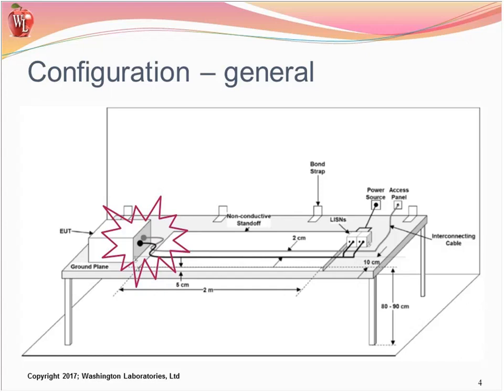Now, in the area it shows, I particularly chose an item with no ground plane, or an elevated ground plane above the ground plane. So the 5 centimeters height for the cable routing is above there. Now, if you do not have a ground plane associated with your test article, in other words, it's a tabletop item that is used in a handheld mode or something, but it still has a LISN connected, you need to provide a partial ground plane for the LISNs to be grounded and tied to the enclosure, but the rest of the table has nothing there, and the cables are placed onto the surface of the table. And the height is still 80 to 90 centimeters, so nothing's new there.